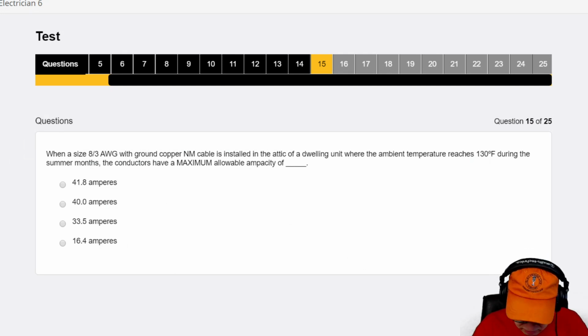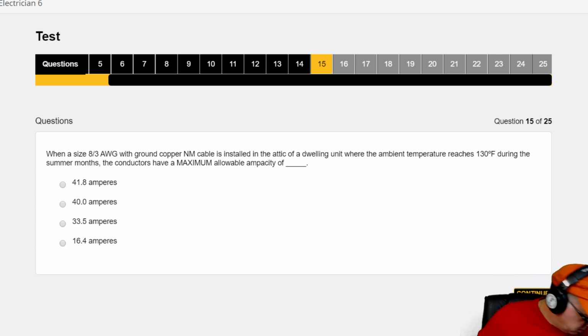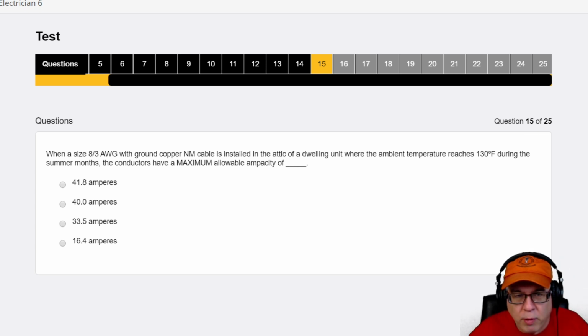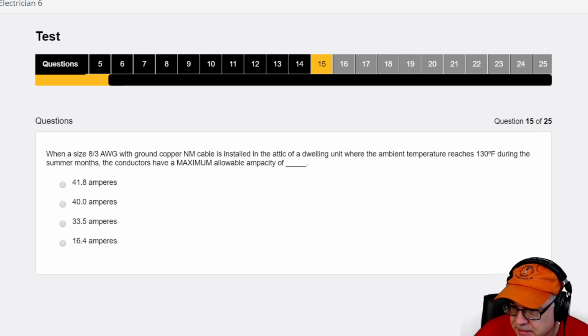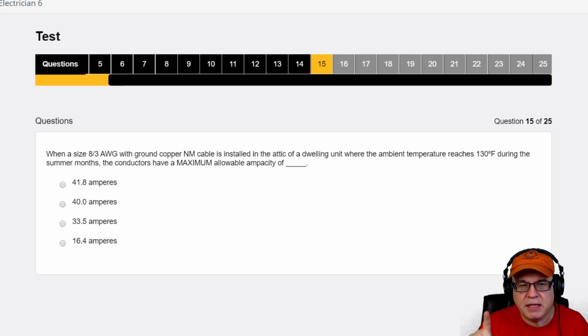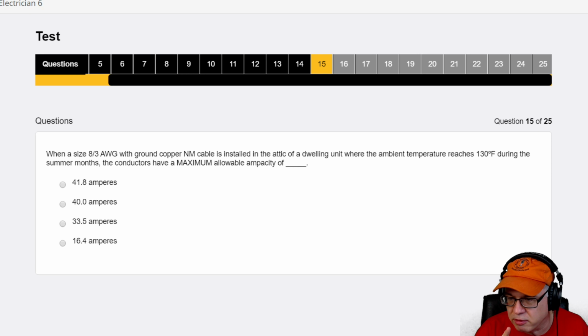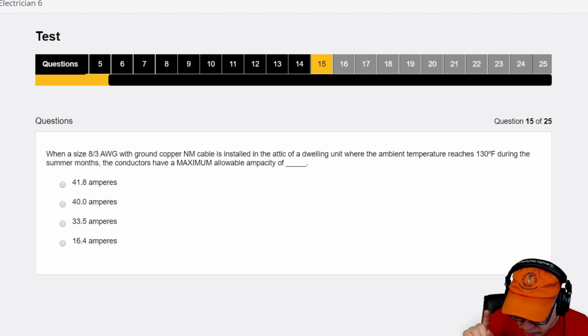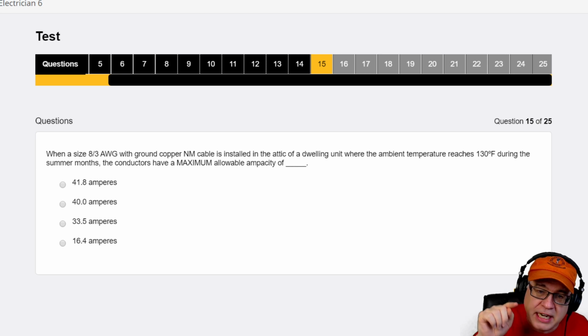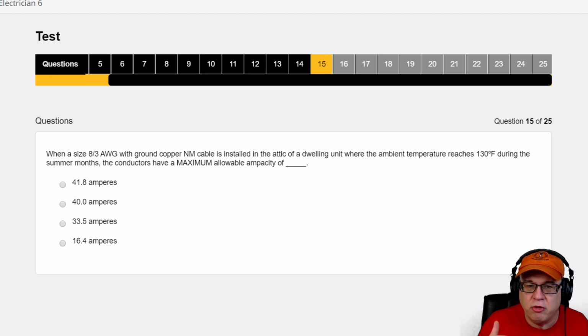So I had 55 amps. So 55 times 0.76 is 41.8. And I'm looking at dropping stuff on the floor. So I have 41.8. Okay. Now, if this question was based on a 60 degree, okay, 60 degree. Now, incidentally, I will tell you this. 41.8 is equal to or greater than the value in the 60 degree column, so that I still can use the ampacities up to 40 amps. Okay, that's kind of a beautiful example.